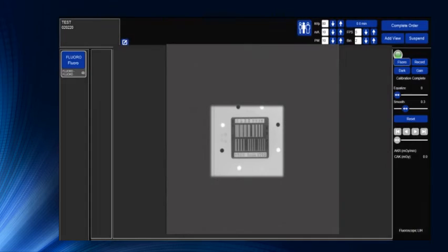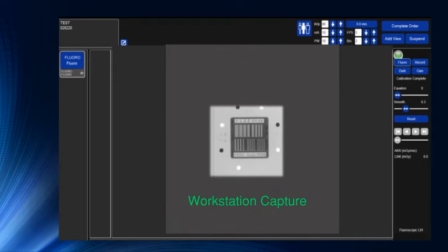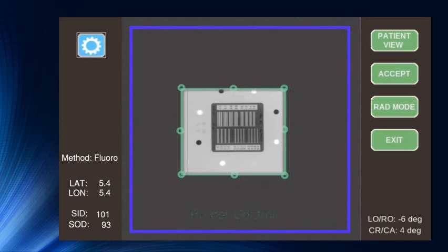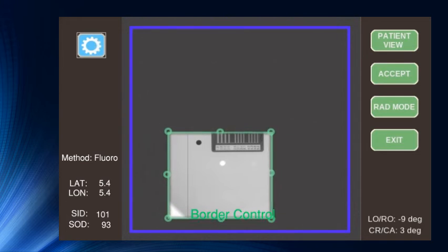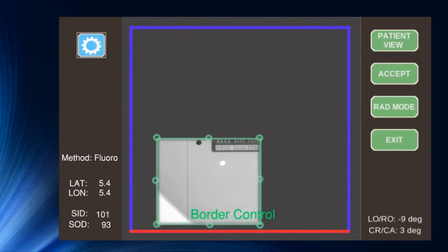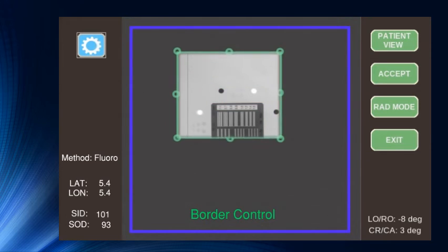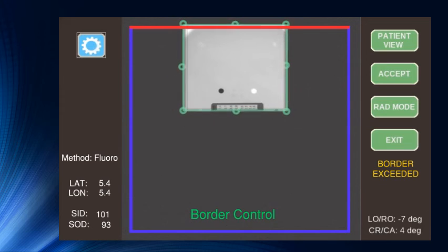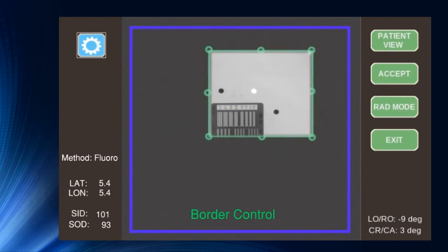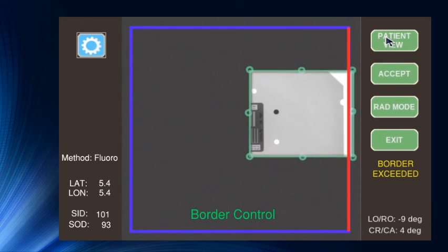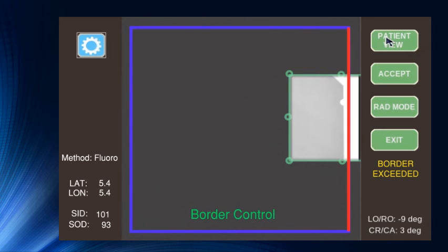Now that the X-ray source is aligned, and the collimated area is adjusted for the anatomic region to be examined, the system is ready to acquire fluoroscopic images using the techniques associated with the selected protocol. During the fluoroscopic image acquisition, each frame of the image is analyzed to determine if the exposed area of the detector touches any of its borders. In the event the image area approaches or touches the detector borders, the MVC will attempt to reposition the radiation beam towards the center of the detector. If repositioning of the radiation beam cannot satisfy the border constraints due to the mechanical limitations of the MVC, the radiation exposure will be immediately terminated so as not to expose the patient to additional, unnecessary radiation. In this event, an error message is displayed, and the user is instructed to realign the X-ray source or detector in order to continue.